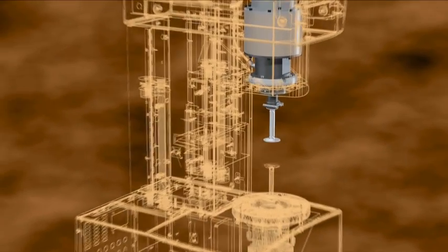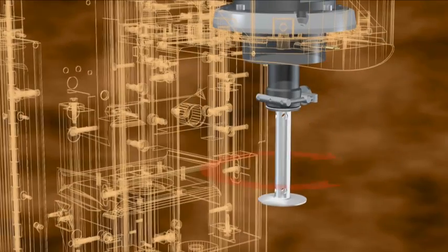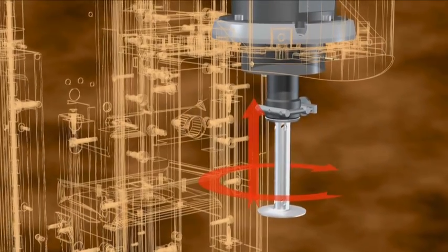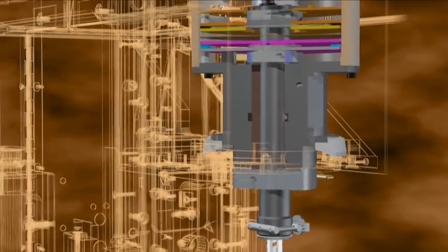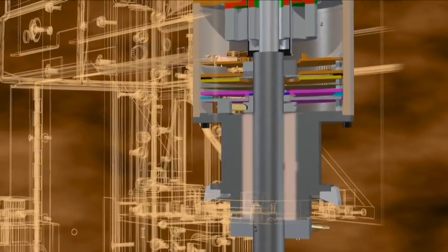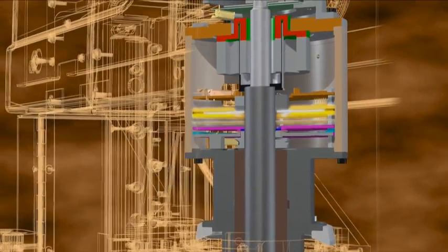The ARES G2 transducer directly measures torque and normal force. New features of the transducer include a five-million-to-one dynamic range, a robust air bearing, and a high-resolution capacitive angle sensor.